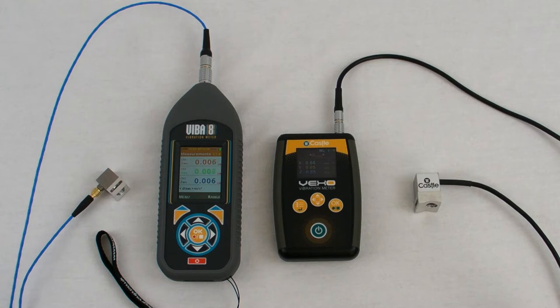The meter must measure the vibration with the hand-arm frequency-weighted filter, WH. Without this filter, the results will be useless and there is no way to correct for it afterwards either.